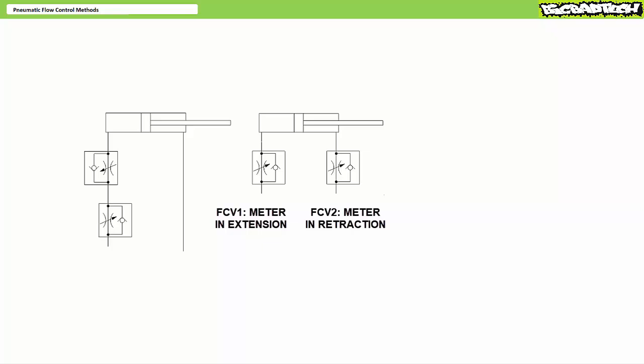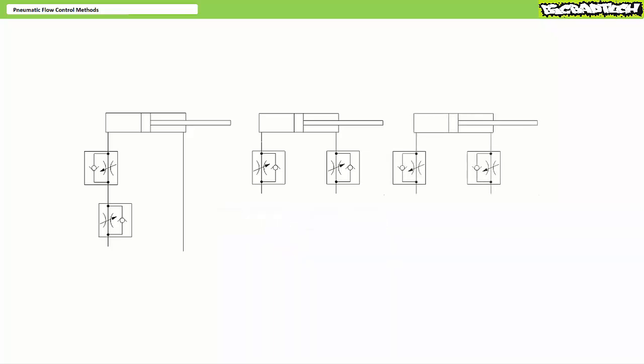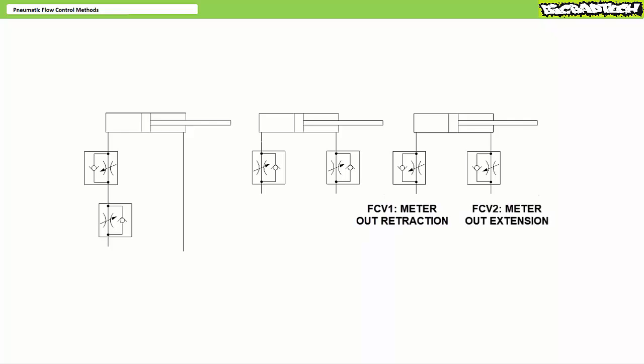If one kept the flow control valves with check valve bypasses in place, yet flip-flopped their orientation, you'd flip-flopped their function. In this implementation, flow control valve one on the cap end establishes a meter out retraction arrangement, whereas flow control valve two on the rod end establishes a meter out extension arrangement. You may wish to pause the lecture and stare at these different configurations to discern the differences if they're not immediately identifiable.